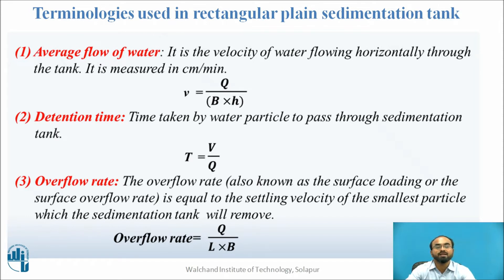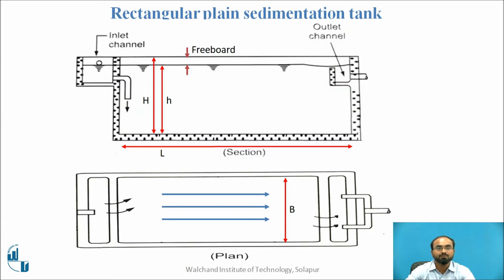The third parameter is overflow rate. Overflow rate is the settling velocity of the smallest particle present in the sedimentation tank that must be removed. It is also called surface loading rate or SOR. The formula is capital Q divided by L into B, where Q is discharge, L is length, and B is breadth. Note that the area used here is the surface area (length × breadth), not the cross-sectional area, since the particle settles in the vertical direction.